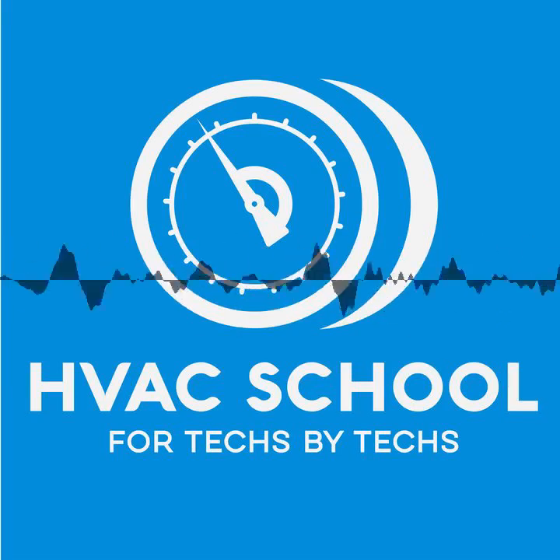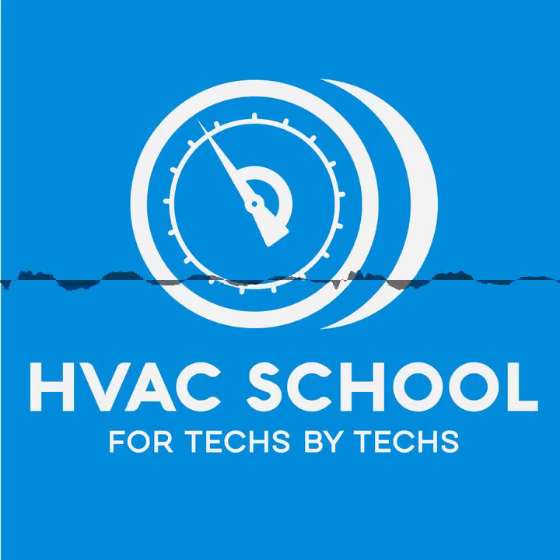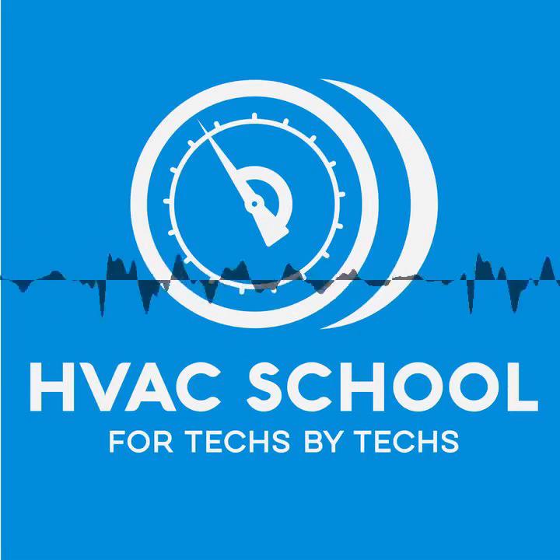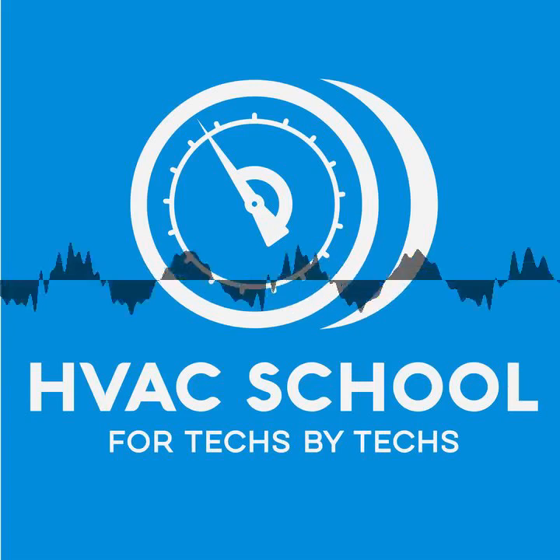So the original 90-plus furnaces, realistically, all they did was cool the flue gases down. In fact, there was very little condensing that took place, if any. If you go to an old 90-plus furnace and pull the condensate drain off and watch it run, you might get a drip or two of condensate as it's running. It was still called a condensing furnace because it ran at the threshold of condensing, but it really didn't condense much of the heat energy out. Now you get into a 97% efficient furnace, and it'll run a 1/8 to a 1/4 inch stream out of that same trap, because now we're extracting additional heat energy out of the flue gas and we're deeper into the condensing range.